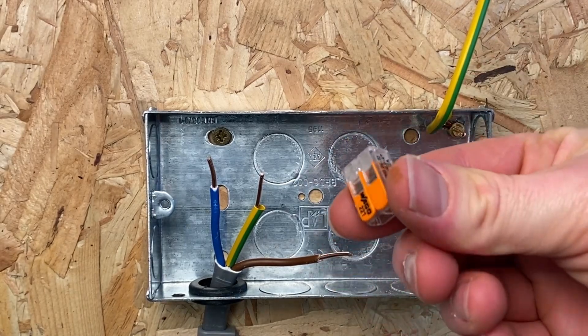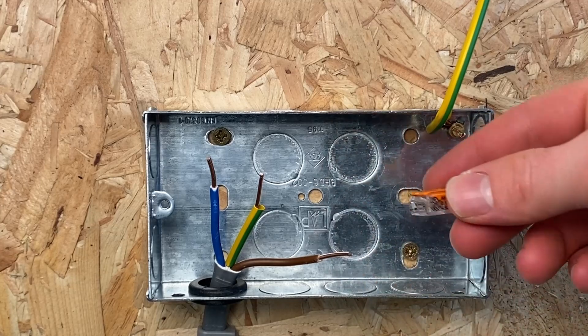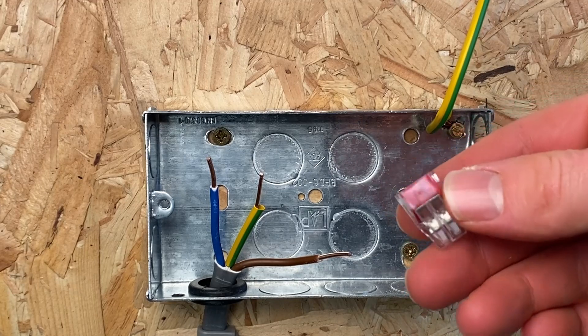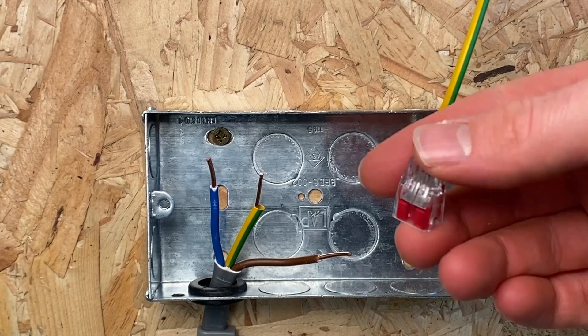The next option is a regular Wago - you don't actually have to use one of the inline ones. Especially in a box where you've got enough space, you can just use one of these connectors. Other options are a similar Ideal version of the Wago, but this one can't be removed very easily either - there's no lever to pull it out, so once it's in, it's in.